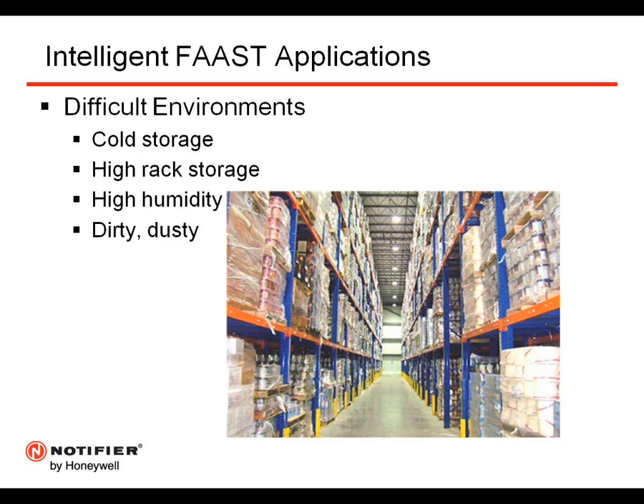One could be that as you're looking at high rack storage, maybe their thought was to potentially use beam detectors. But as that beam detector is going through that space, it might not be suited because they're storing stuff that could be blocking the beam, or they're moving things around with forklifts that could potentially block that beam and either cause troubles or potentially cause a nuisance alarm.